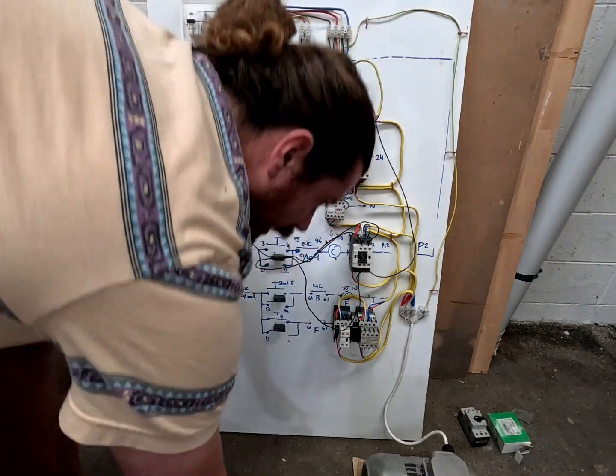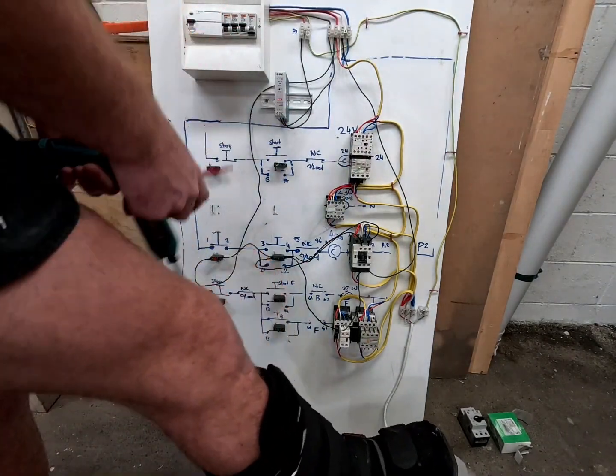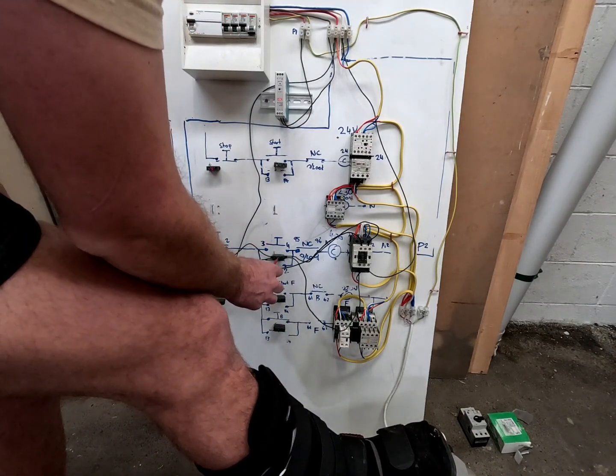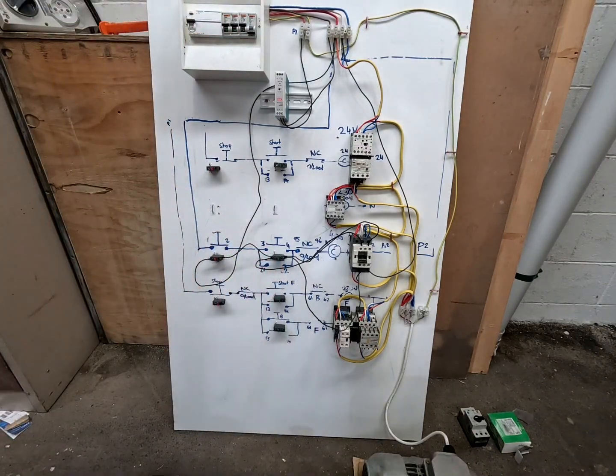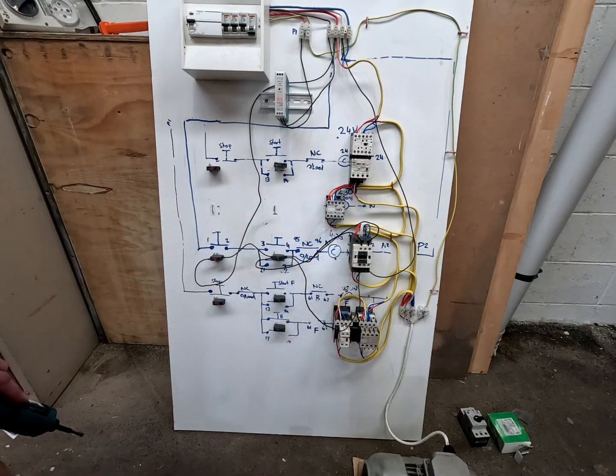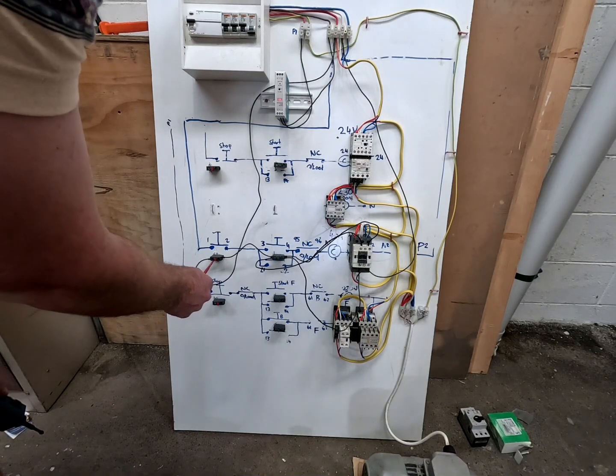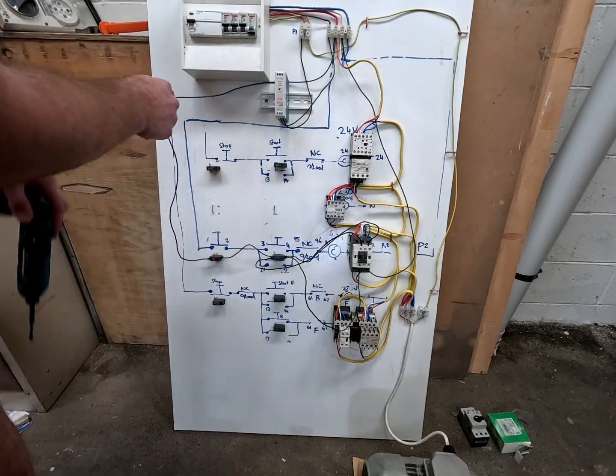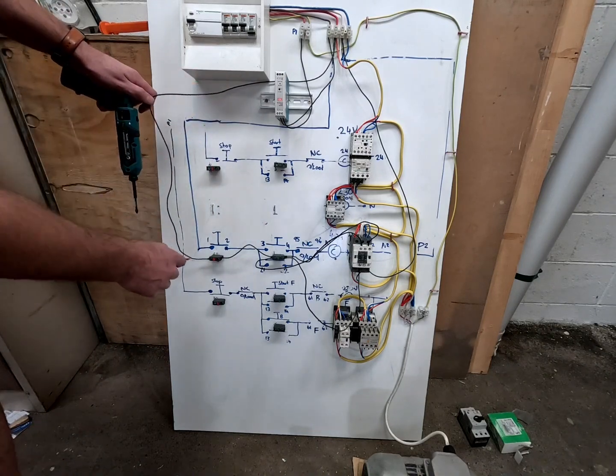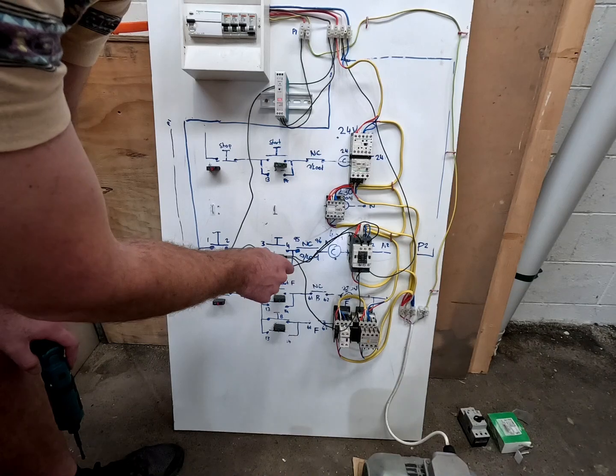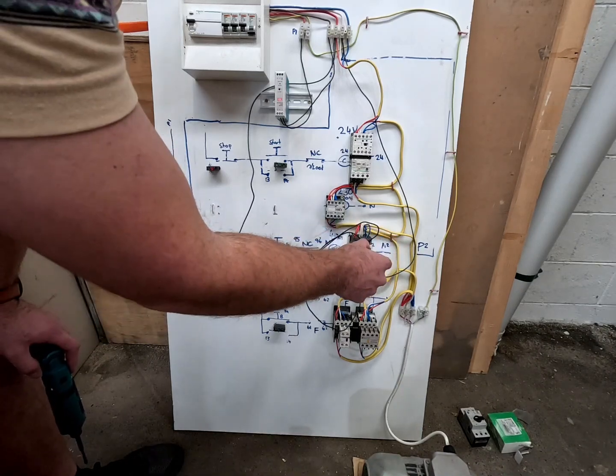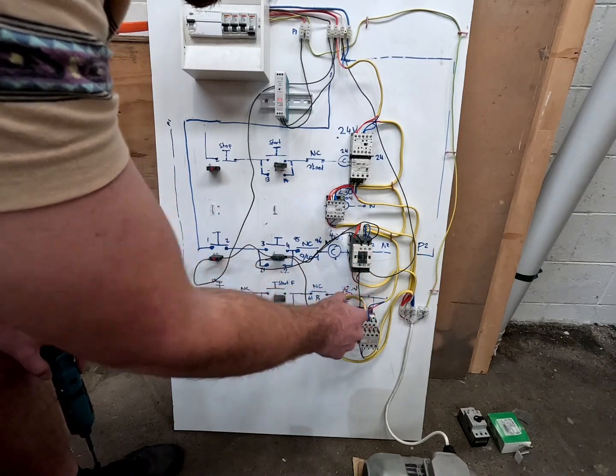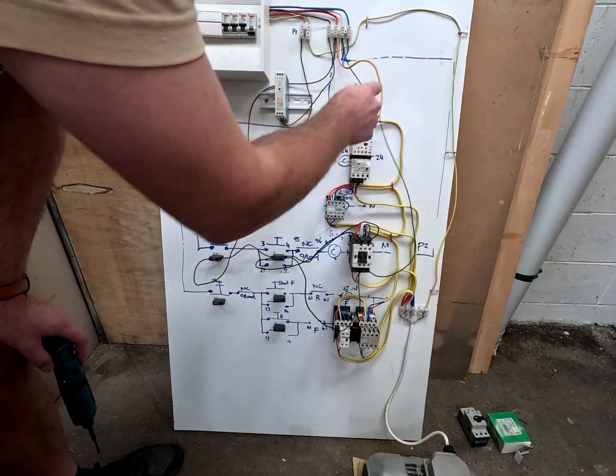We're all live at the moment, my foot on the motor until we're ready to go. You can press start and the motor's running, holding the contactor in. It's all going just fine. Press the stop button and it turns off. So remember, first phase comes down here through the stop button, which is normally closed, onto the start button, which is normally open, through to the hold-in contact which is in parallel, and then out onto phase two.